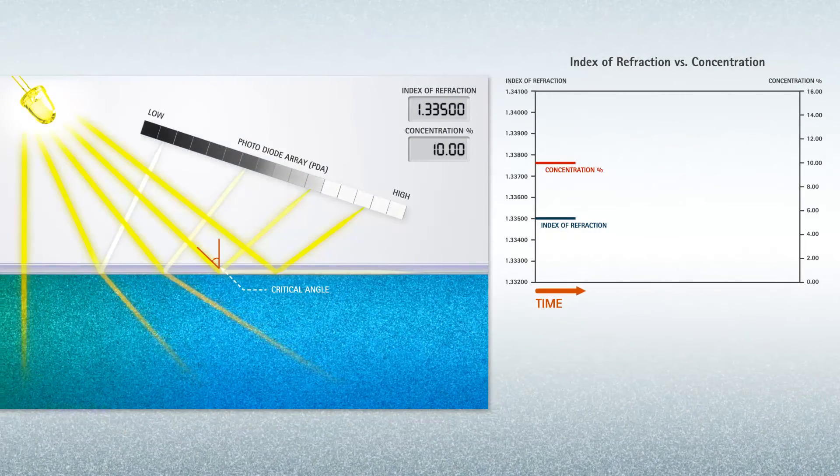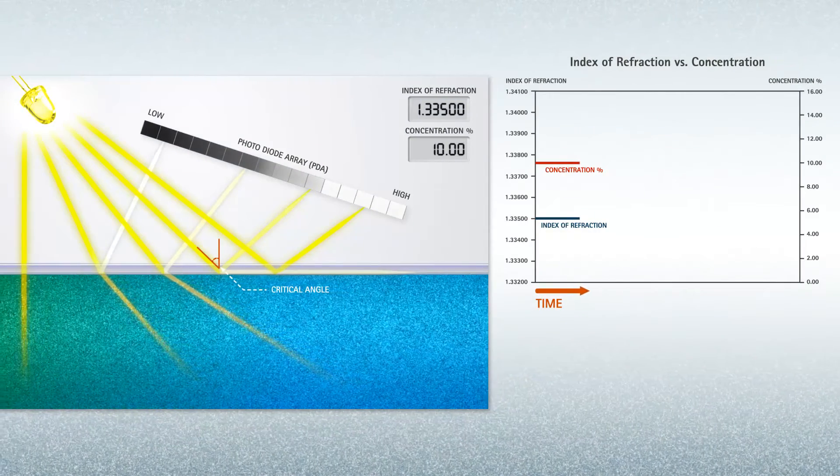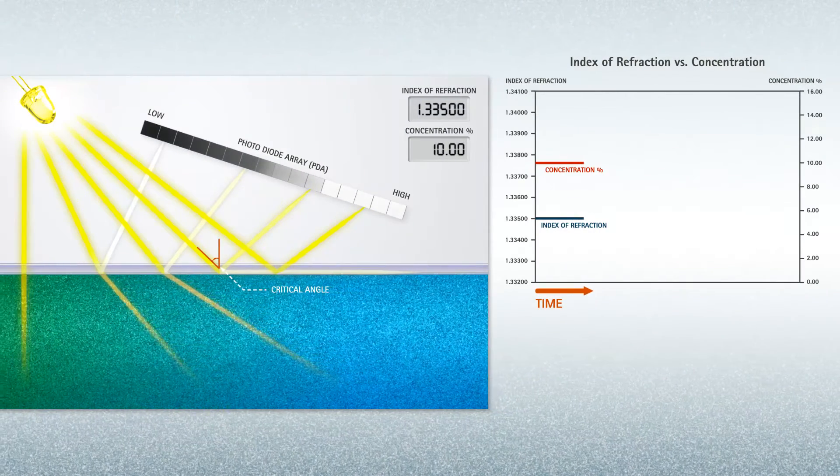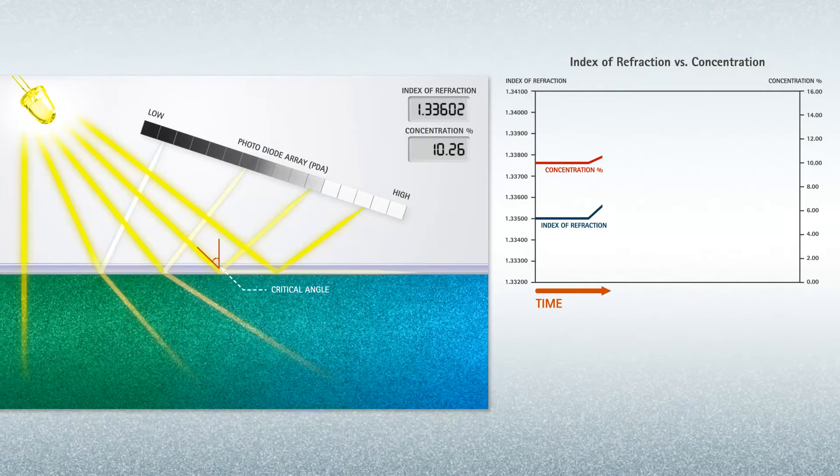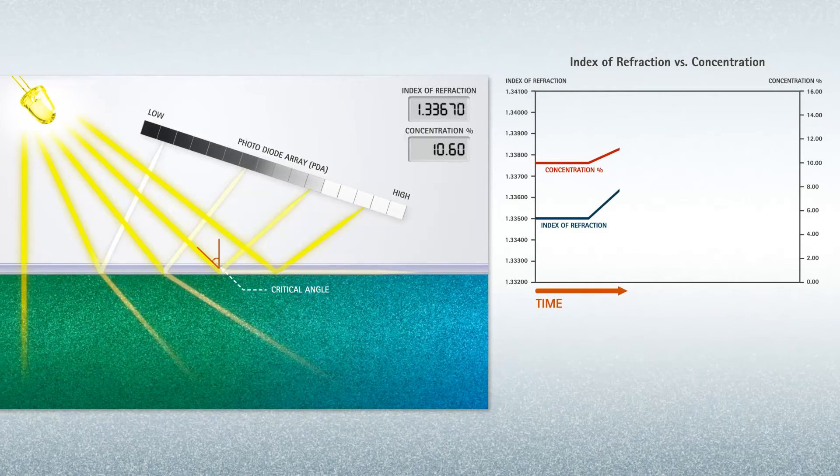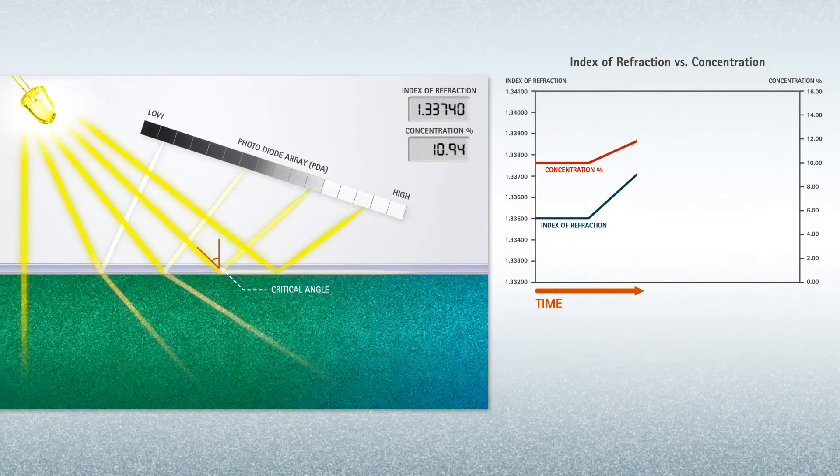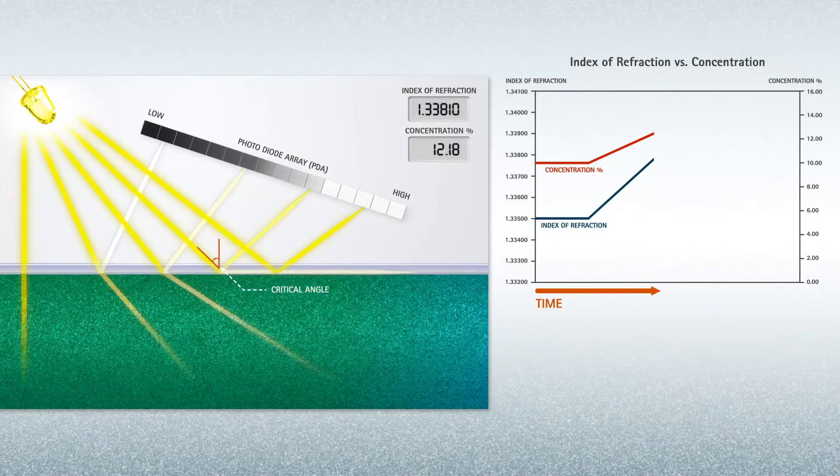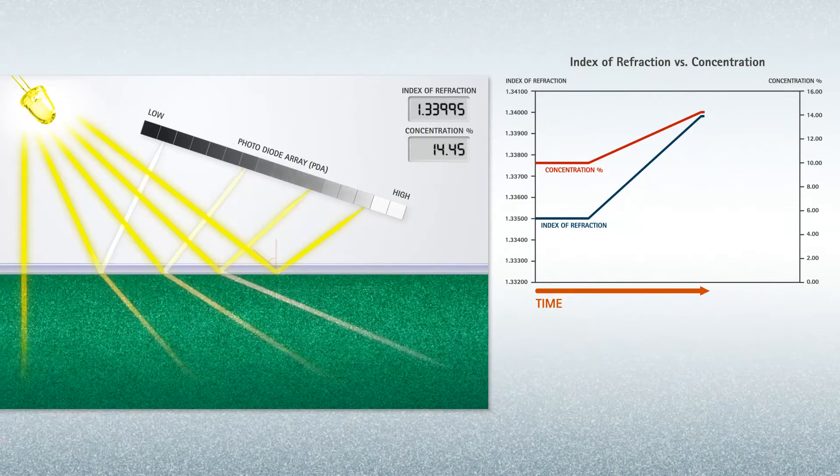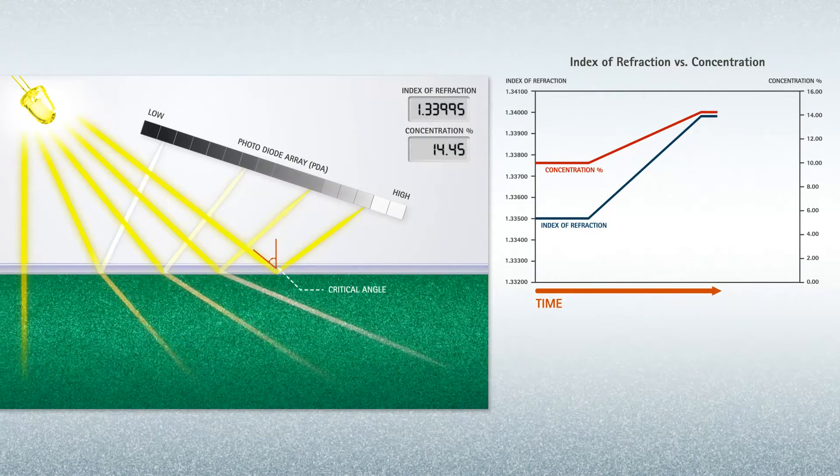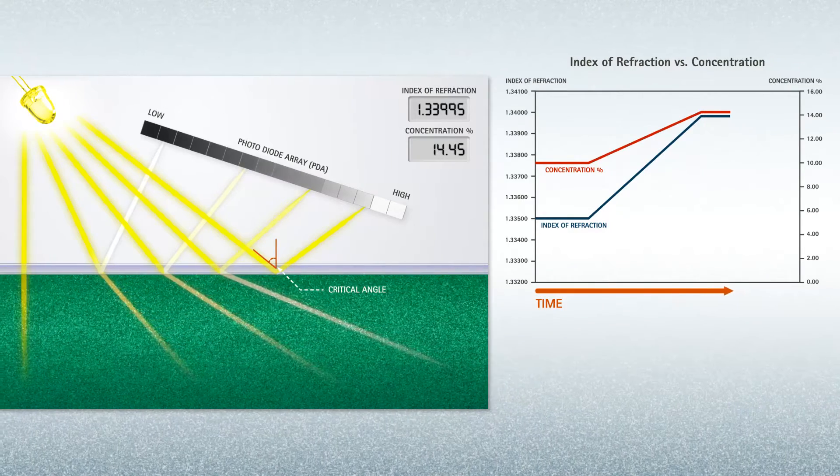As the liquid concentration changes, so does the measured critical angle. The Index of Refraction measurements are continuous, while at the same time, average readings are made every 100 milliseconds.